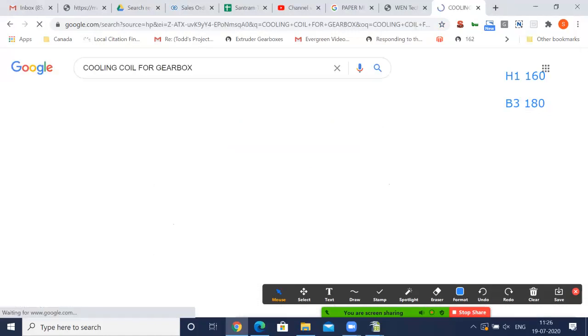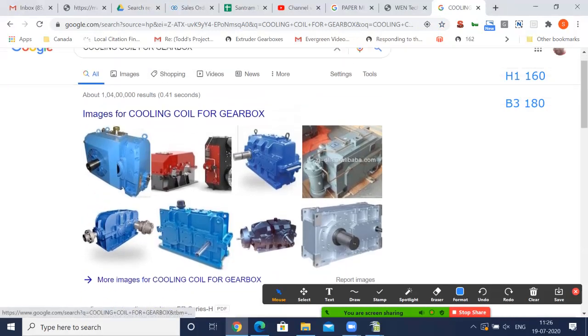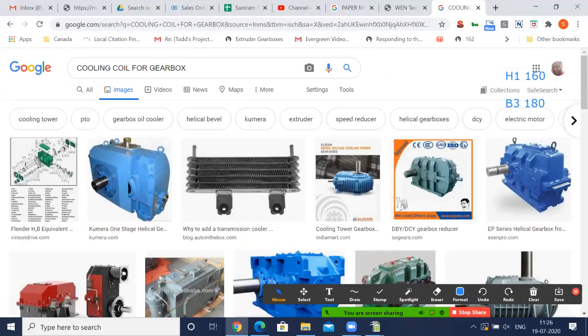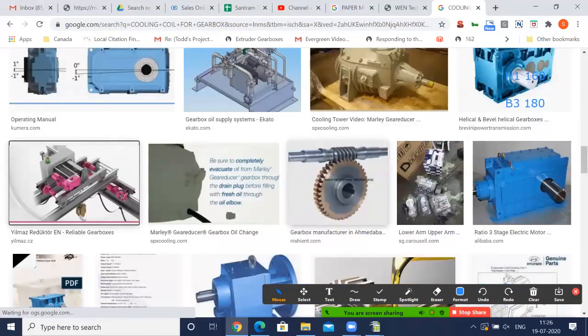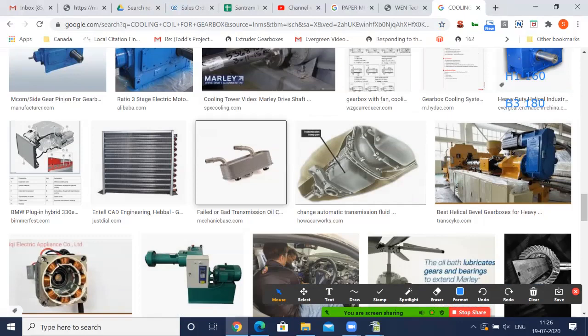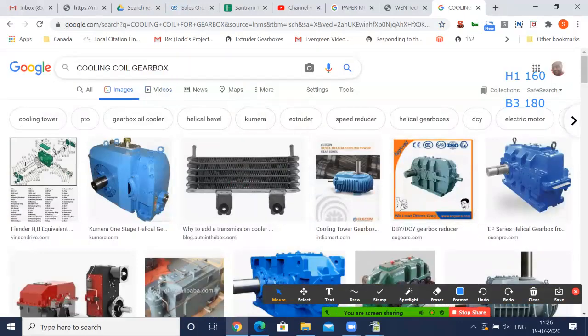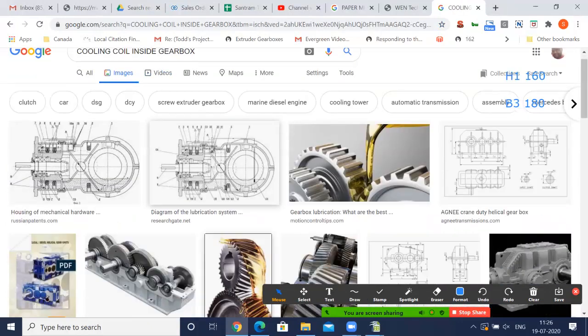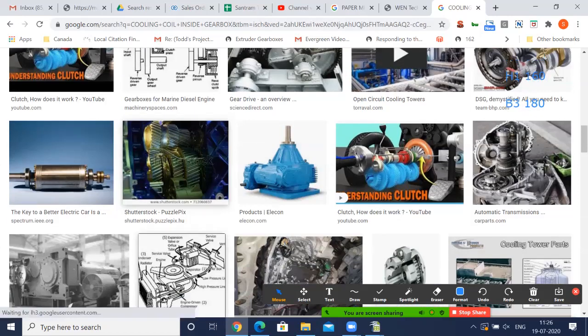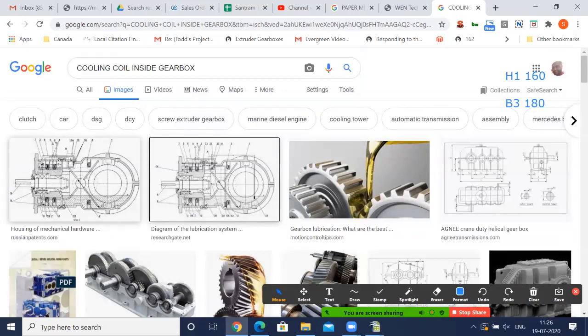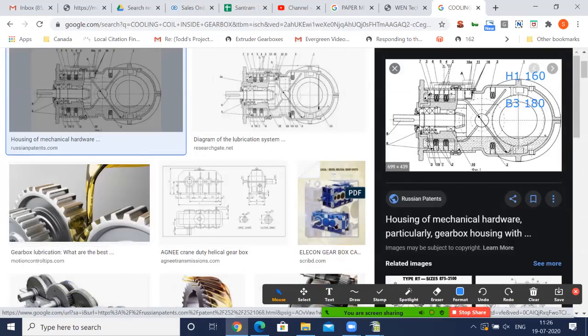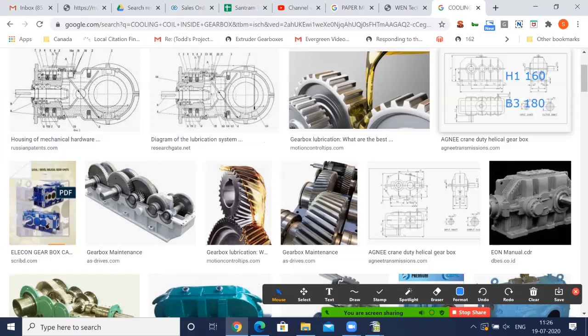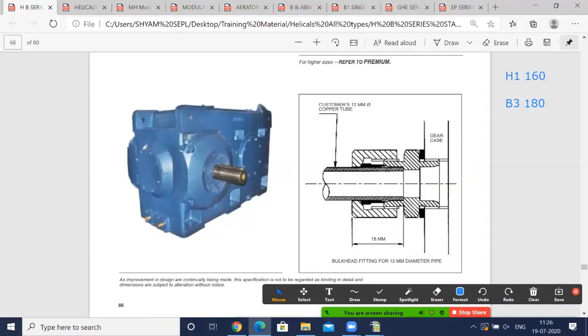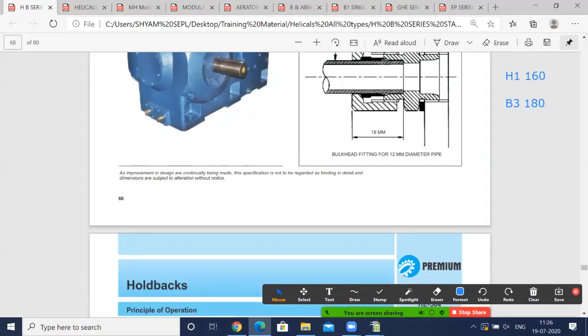So see inside image, if you can see online, I'll just show you what a cooling coil is. It's not like this. Basically inside it's just the coil. If you can see somewhere, cooling coil. Which is hard to find online because it is something that is internal. Okay, but it's basically a copper tubing. Okay, in this image, if you can see this piping inside, not from place to place, it's just at the bottom of the gearbox just to make sure it comes in contact with the hot oil and cools it down. Okay, so that is a cooling coil. So it will always be at the bottom of the gearbox, as you can see here. Okay, inlet and outlet for water. It is just for water.